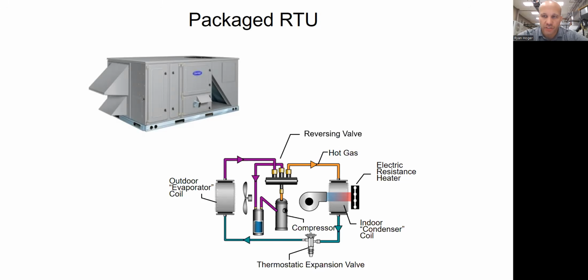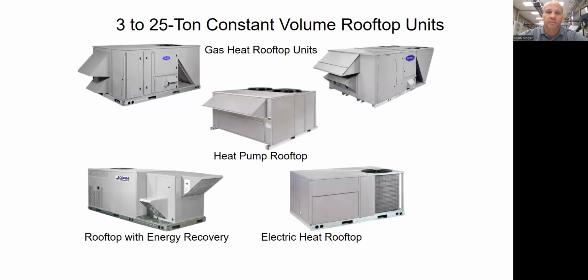If we do a heat pump version of these, which we'll talk about more later on, everything's going to be the same in there, except we're going to add that reversing valve, just like we did last session. There's a couple other little components from a control standpoint too, but from a mechanical moving parts perspective, the reversing valve was the only extra thing we add to the system when we designed it to become a heat pump version of the same system. And that allows us to do heating by extracting heat from the outdoors and putting it to the indoor air. If you don't know what I'm talking about, you definitely need to go watch session 1.